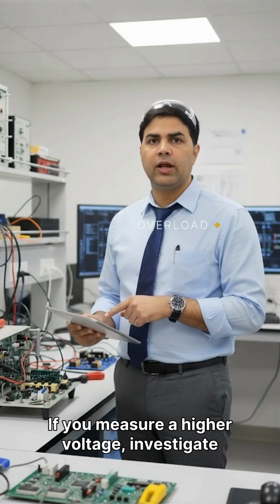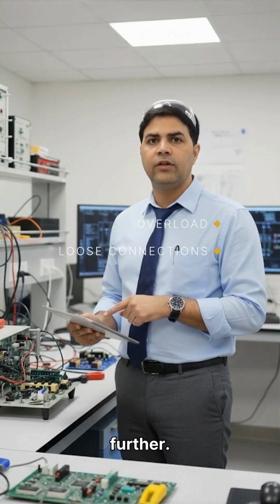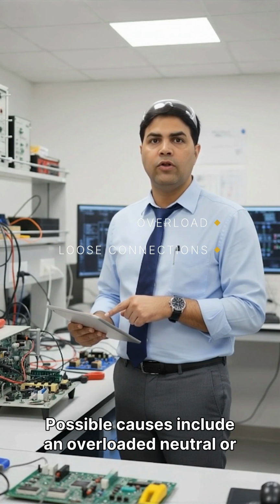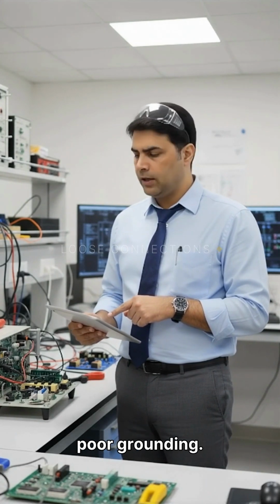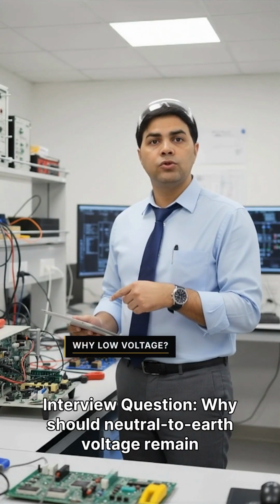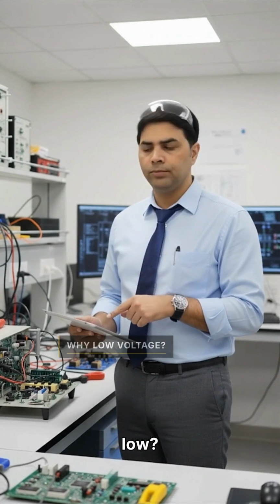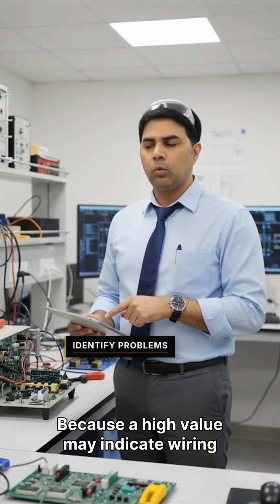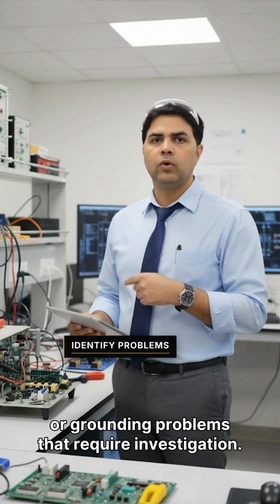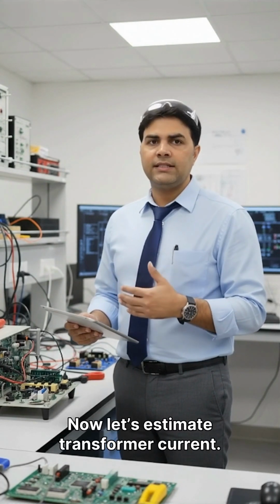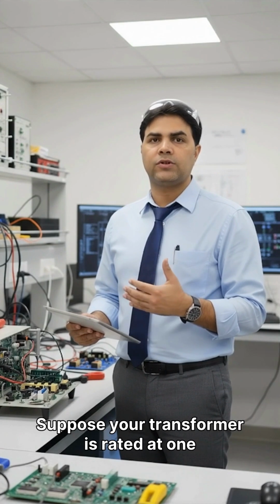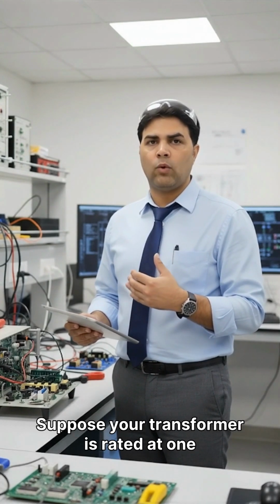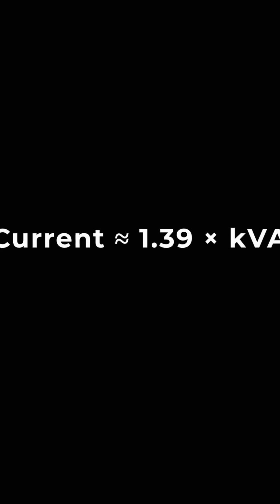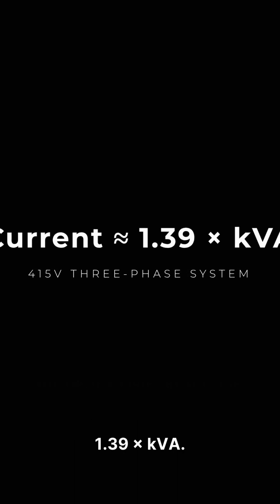If you measure a higher voltage, investigate further. Possible causes include an overloaded neutral or poor grounding. Interview question: why should neutral to earth voltage remain low? Because a high value may indicate wiring or grounding problems that require investigation. Now let's estimate transformer current. Suppose your transformer is rated at 100 kilovolt amperes. A quick thumb rule is current approximately equals 1.39 times kilovolt amperes.